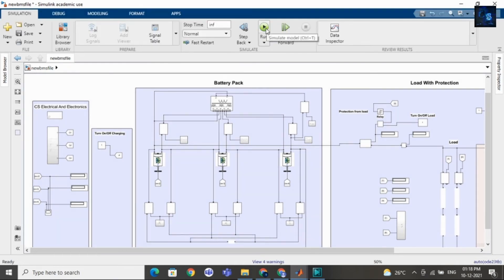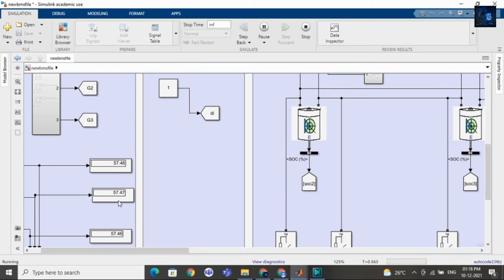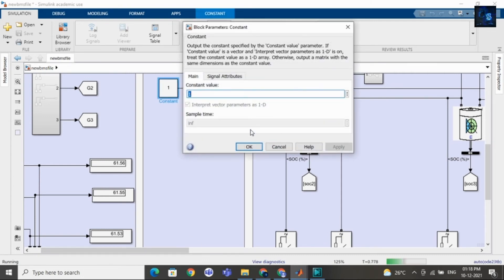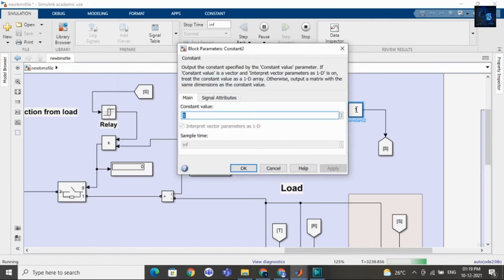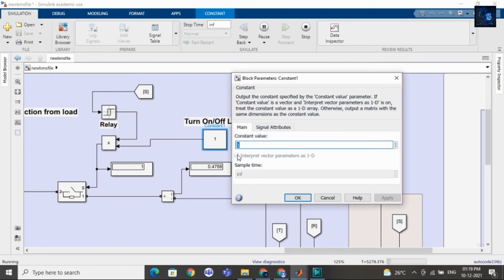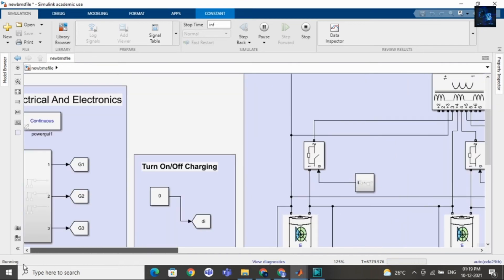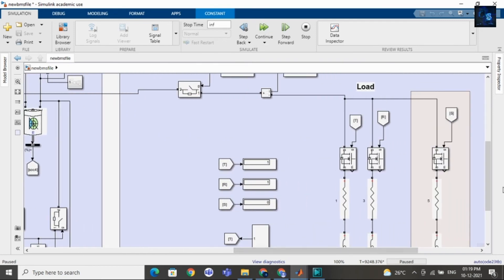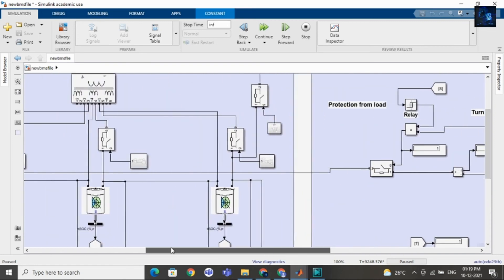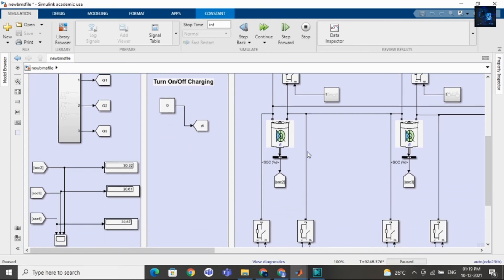I will pause this and run again. Here you can see the SOC value is now equal. Now I will stop charging of this battery pack and connect the load. I will connect load for a few seconds without creating an overload condition. Now the SOC value is 30%. Now I will disconnect the load — we will bring it to around 20%. If the SOC is less than 10%, it will become bottom balancing, so we will keep it more than 10%.